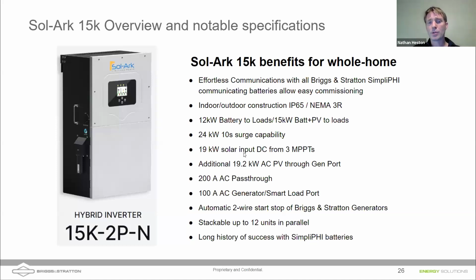You get 200 amps of pass-through. That's the big thing. This is really the big difference, that 200 amps of pass-through with this inverter. Other inverters don't have that. And so that ability to just pass all of that utility power through the inverter to the loads panel is what allows us to easily do whole home backup with just a single inverter. You can integrate up to 100 amps of AC generator coming through, so 100 amps, 240 AC. You get automatic 2-wire start, and you can easily interface with our Briggs & Stratton generators. We have many examples of Briggs & Stratton standby generators being controlled by the 2-wire start of Sol-Arks.